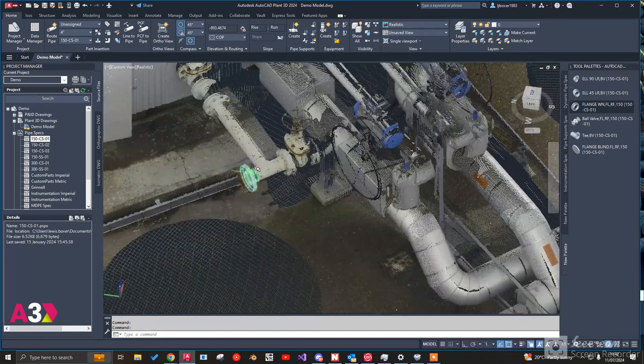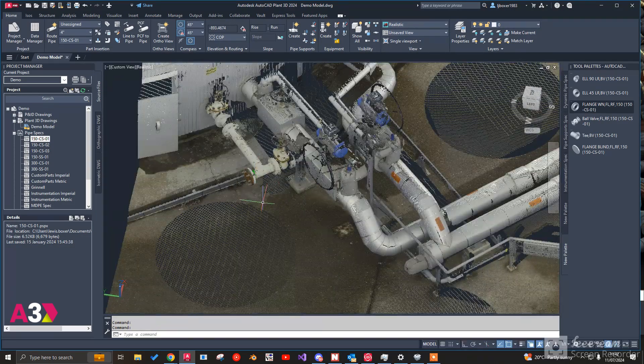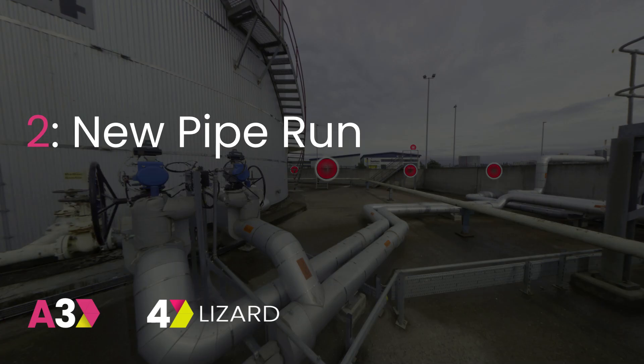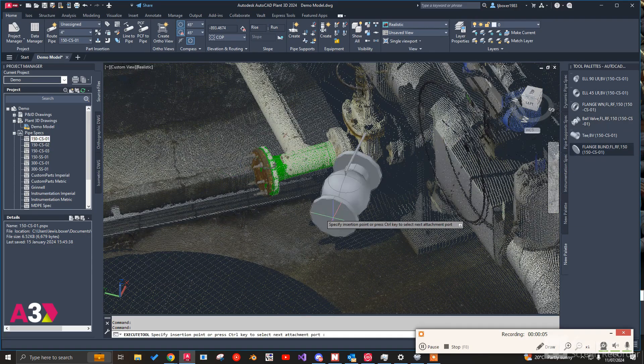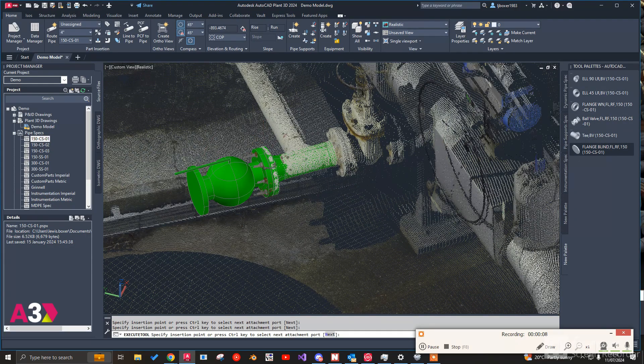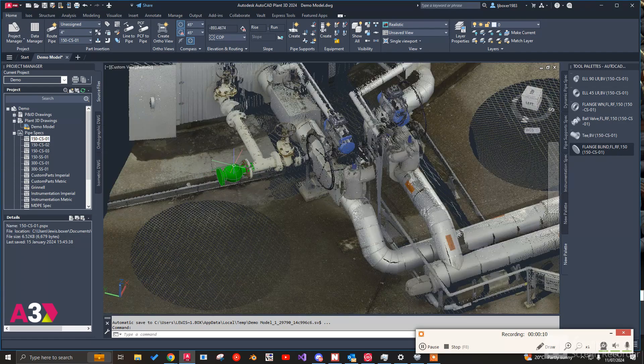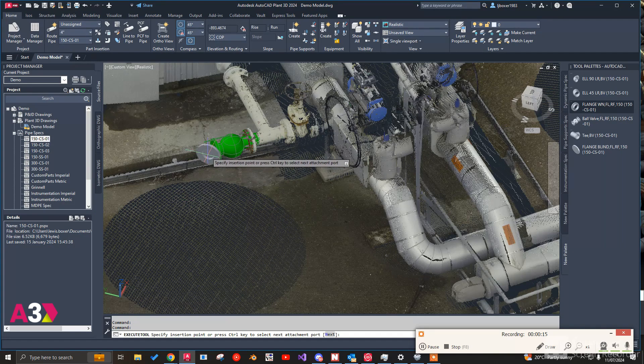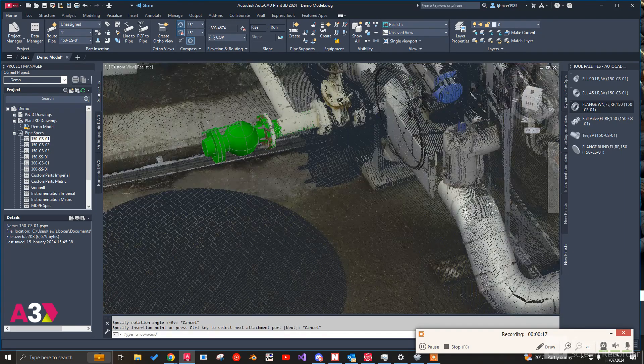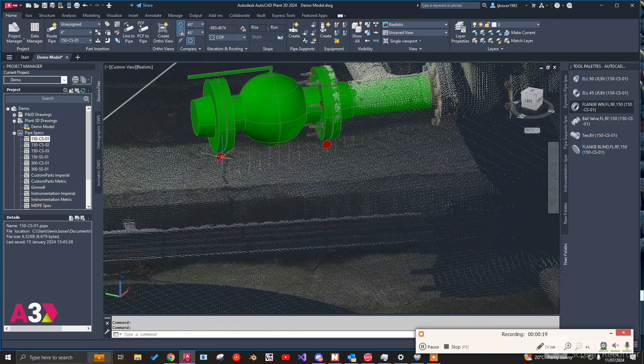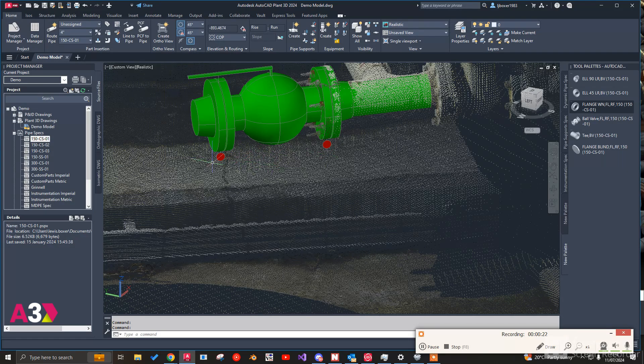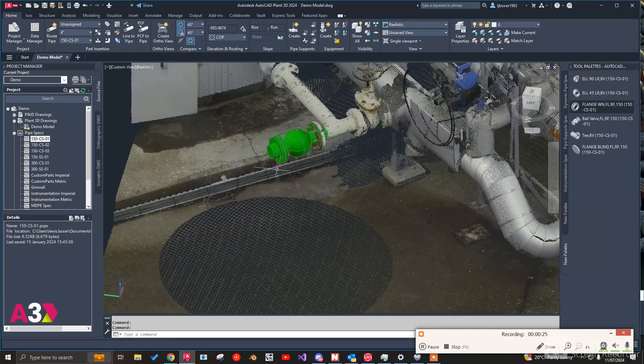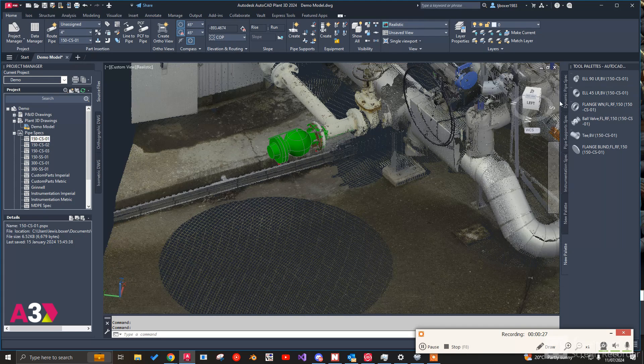So at this point we've got our existing line modeled in. So we can now look at modeling the new line. So I think the best course of action is to put a ball valve in so we've got the ability to isolate this line. And then we're going to put another weld neck flange on. You'll notice that as soon as we put that weld neck flange on both sides that it's automatically put the gasket in and it's automatically because of the spec being set up put in the bolt set as well.